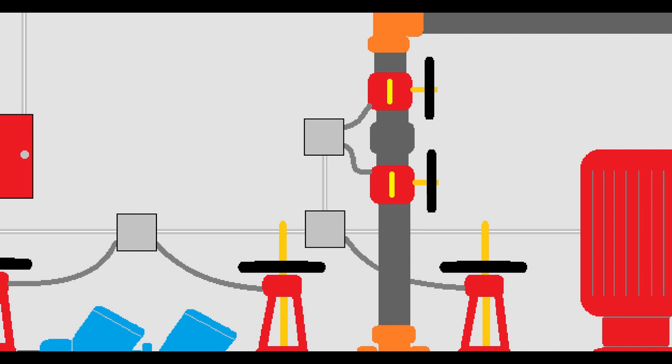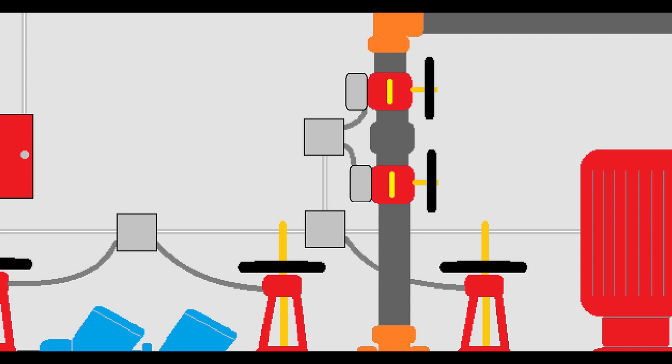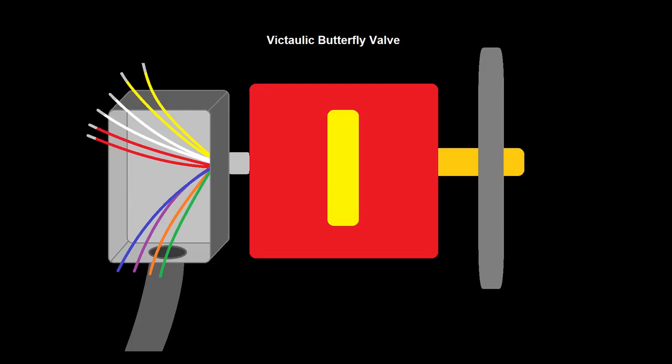Butterfly valves come with a bunch of wires sticking out of them that we wire into the fire alarm circuit. We usually install a small single gang handy box on the outside of these with a close nipple and make the splice to our fire alarm circuit in that box. Different manufacturers of these valves use different colored wire, so just like with the OS and Y valves, it's best to meter these first before making any connections. When the valve is in its open position, the yellow bar on the outside of the valve housing will be parallel with the sprinkler pipe. When the valve is shut, it will be perpendicular to the sprinkler pipe. Regardless of the manufacturer, these valves almost always come with two different sets of wires. The first set would have two of each color, though sometimes there are only two of the normally open pairs. In this case, we have two common, two normally open, and two normally closed. Then there's a set of auxiliary contacts that you could use for another purpose if desired, but they're usually just taped off inside the handy box. The green wire is always a ground connection.